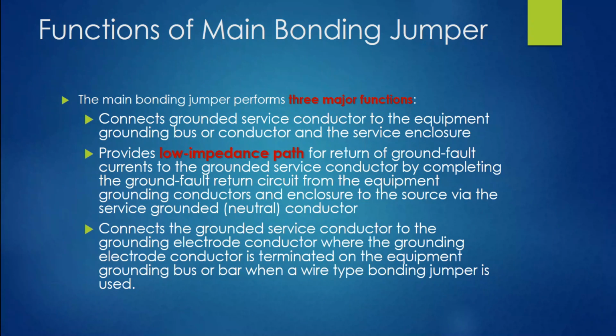Now, what are the functions of the main bonding jumper? Not to get repetitive on that, but I think it's critical that we reiterate that it connects the grounded service conductor and the equipment grounding bus or conductor in the service equipment. It ties everything together. It provides that low impedance ground fault current path for current to get back to the source. That's a key thing to allow any overcurrent protective device downstream to actually trip.